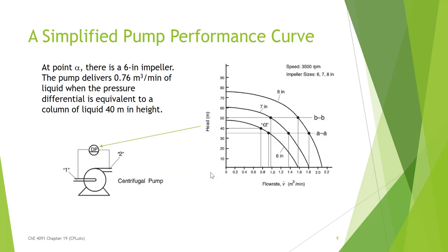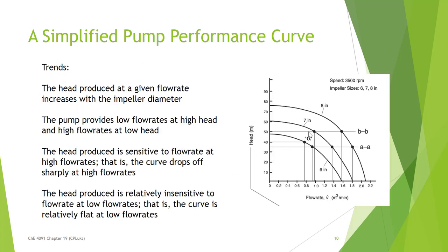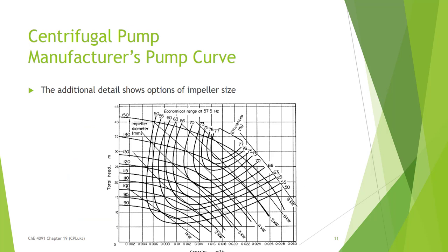This is a simplified pump performance curve. There's a great example in your book that I really recommend you read — they go through it for various sizes of impellers. If you look at the flow rate and the head, for instance at point alpha, where we have a 40-meter head, we have a flow rate of just less than 0.8 cubic meters per minute. They also discuss how, if you keep the same head but change impellers, with a larger impeller you're able to get a larger flow rate. Manufacturer curves look a lot more complex because they include information for many possible sizes. I will link you to a video that goes through this in great detail.